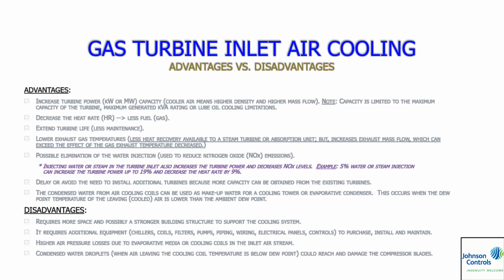The lower gas exhaust temperatures. Now, there's some heat recovery processes out there where you take that 1,000 degrees exhaust air and you can recover it. Okay, use it in like absorption chillers and other processes. So there is an advantage to this. We are lowering the gas temperature, but there is less heat recovery, which is kind of a disadvantage. I've got it under advantages because there is a benefit to lower gas temperatures. So we have less heat recovery, but we've increased the exhaust mass, which can effectively affect the gas temperature decrease. So they kind of all offset each other.